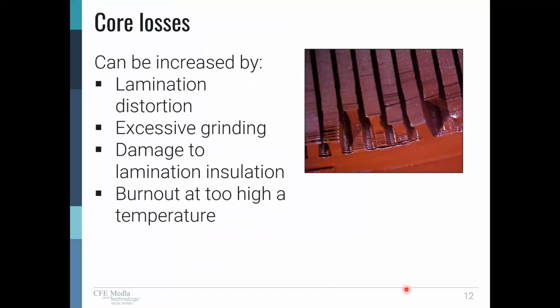Core losses. In terms of repair, our concern is that the core losses can be increased if we distort the laminations. If we see distortion like this, where the laminations aren't perfectly in a straight line, we start losing our symmetry, and that can lead to losses. Excessive grinding: here, there was some damage to the core and it had to be ground out, so there was grinding work done to that. And lamination insulation. These thin discs of steel we see here are less than a 32nd of an inch thick. They're very thin, but they do have a coating. This picture shows some paint, but in between, when they stack this core, it's not paint. It's a special type of coating called core plate that goes on there. Microscopically small, but it is insulation.